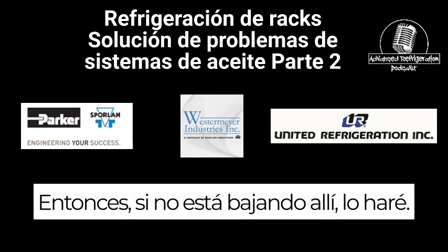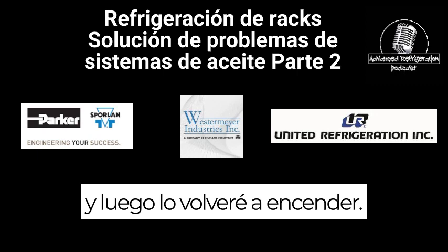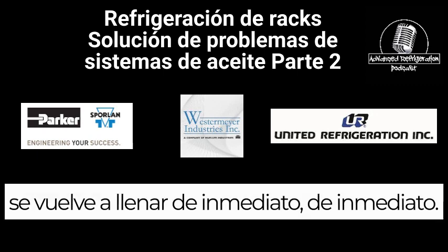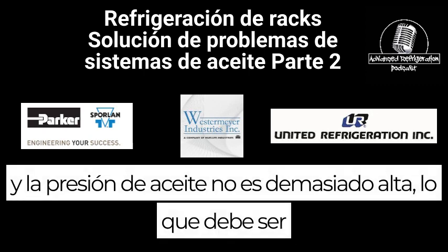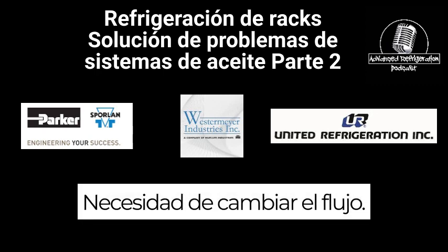So if it's not coming down there, I will generally pump the compressor out into the oil reservoir, and then I will turn the oil reservoir back on, and if it fills back up immediately, right away, then you know the oil flow is bad. If you already reset it back to where it should be and the oil pressure is not too high, whatever it should be, 20, 30 pounds above, then you have an oil flow failure. So you need to change the flow.